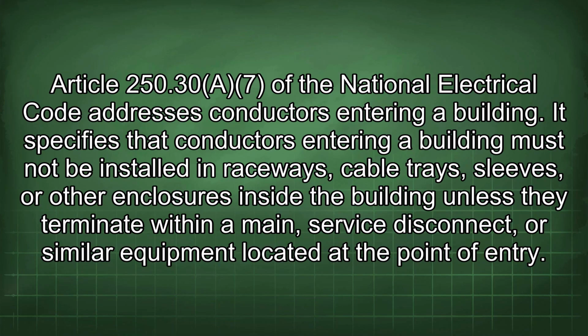Article 250.30(A)(7) of the National Electrical Code addresses conductors entering a building. It specifies that conductors entering a building must not be installed in raceways, cable trays, sleeves, or other enclosures inside the building unless they terminate within a main, service disconnect, or similar equipment located at the point of entry.